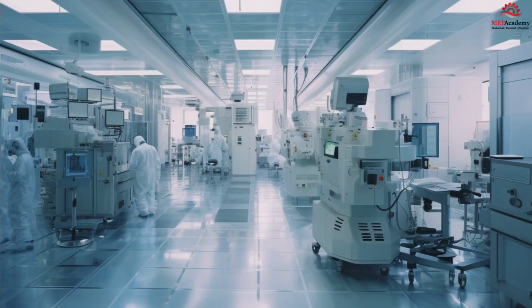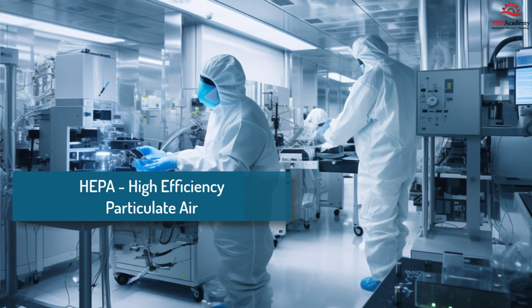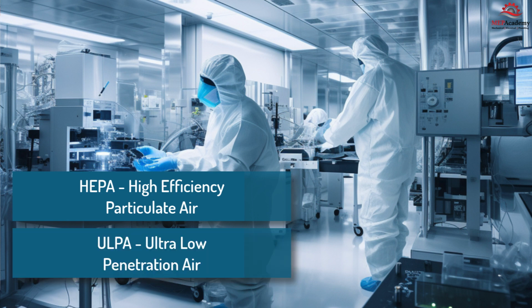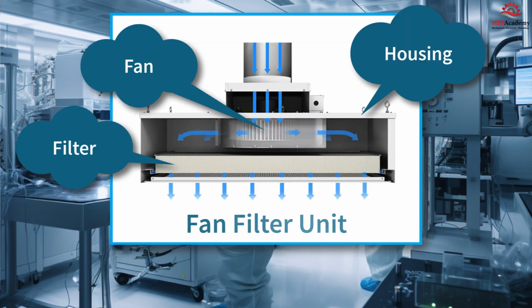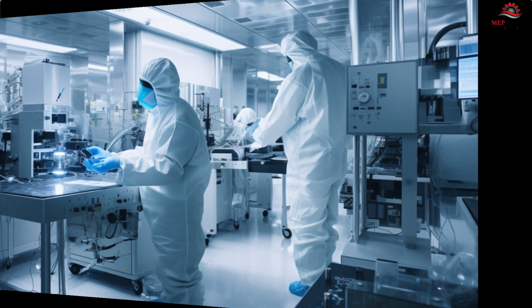A fan filter unit, FFU, is a device used in clean rooms and other controlled environments to provide high-efficiency particulate air, HEPA, or ultra-low penetration air, ULPA, filtration. It consists of a fan, a filter, and a housing unit. The primary purpose of an FFU is to circulate and filter air to maintain a clean and particle-free environment.